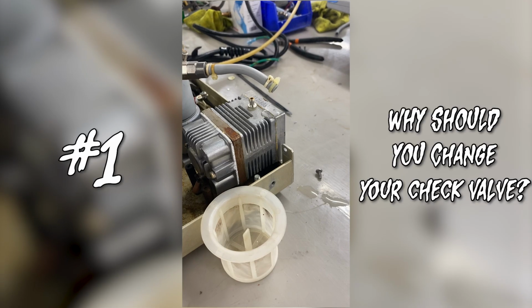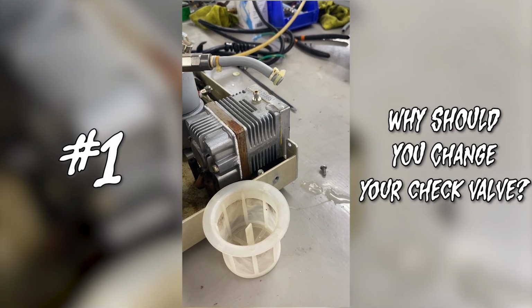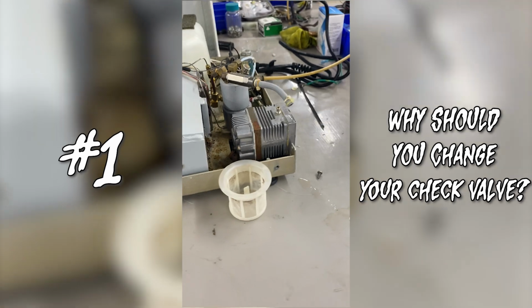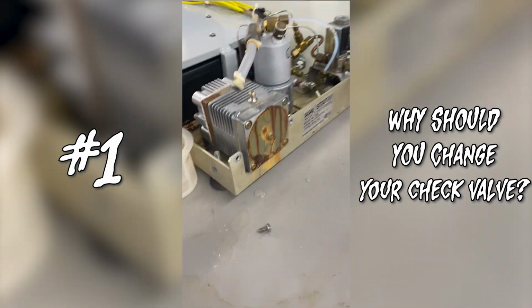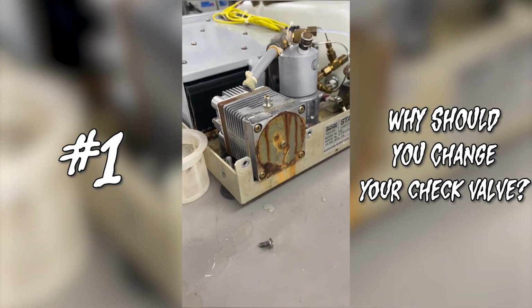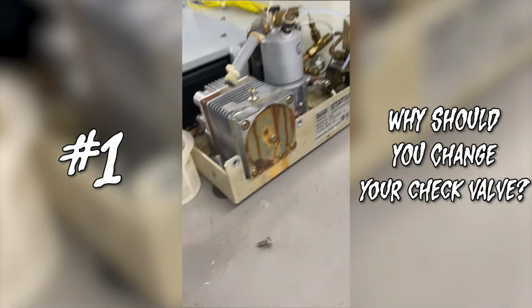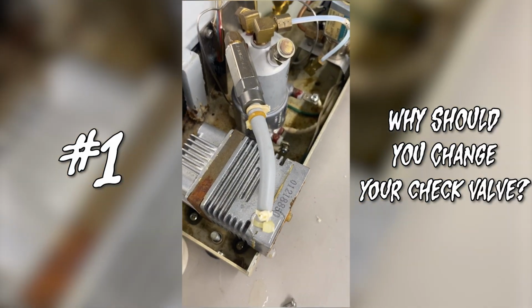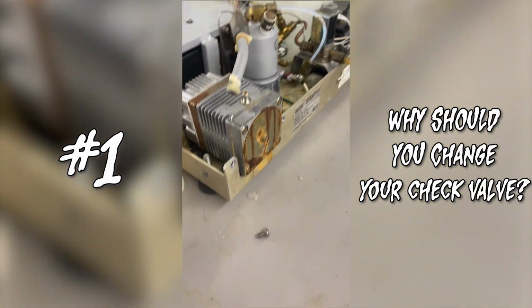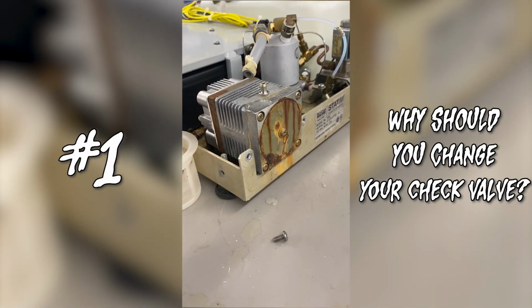is so important. For example, this first entry shows the exact reason why you should always change your check valve on time. A bad check valve can lead to a costly repair. This compressor is completely shot. This check valve right there is supposed to stop steam from getting into the compressor.